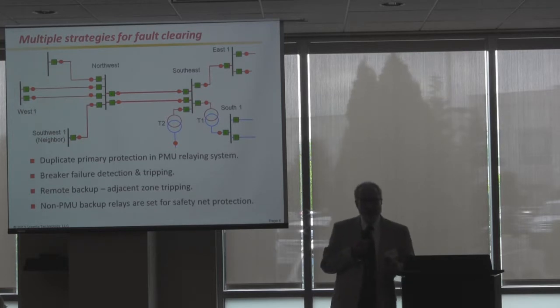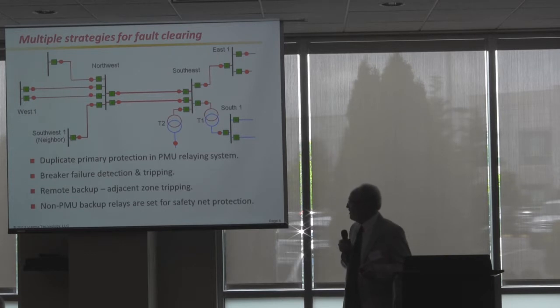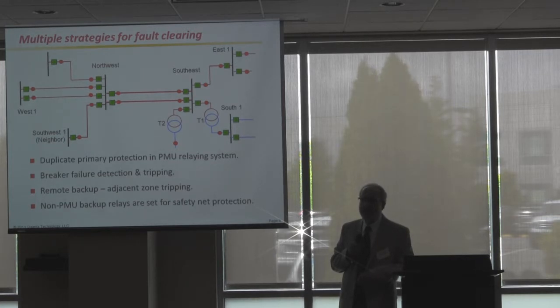Remote backup is tripping adjacent zones when we have no measurements from, or cannot get clearing to occur on, the primary zone where the fault is located. I would not advocate in this work that we get rid of all the distance and overcurrent relays that we have out there, but we fundamentally change their settings so they're slower, farther reaching, and they're aimed at safety net protection and not at the job of backup clearing of faults when the primary systems don't work.